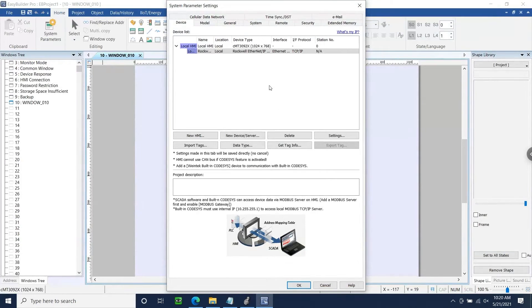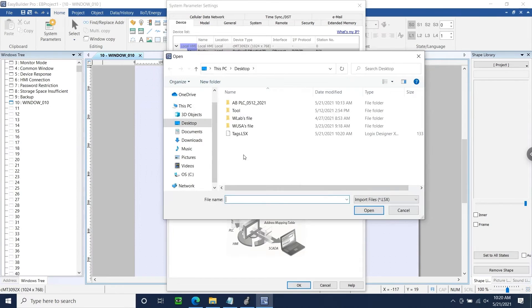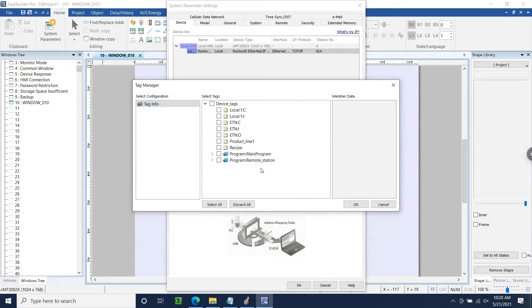Within EasyBuilder Pro, I'll ensure that the driver for our Compact Logix is selected. Below our Device list, I'm going to click Import Tags, and within the following menu, I'll select Import Files .L5X and click OK. When prompted, I'll search for the L5X file within my file browser and click Open, after which the Tag Manager will display, allowing us to select which tags we would like to import within our project.